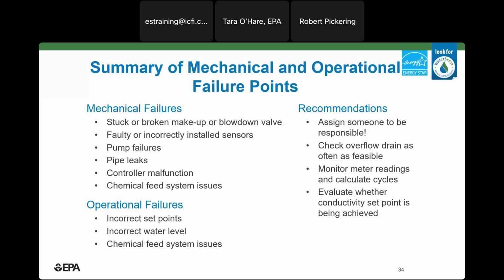They don't necessarily need to be a mechanical engineer to know what to look for during regular check-ins or daily rounds. They should check the overflow drain to make sure water isn't flowing. They should monitor and record meter readings and use them to calculate cycles of concentration. And they should look at the conductivity meter to make sure the tower is operating at its set point. If they do these three things on a daily basis, you can really understand and identify when something is going wrong so it can be resolved before it wastes a significant amount of water and costs you a lot of money.